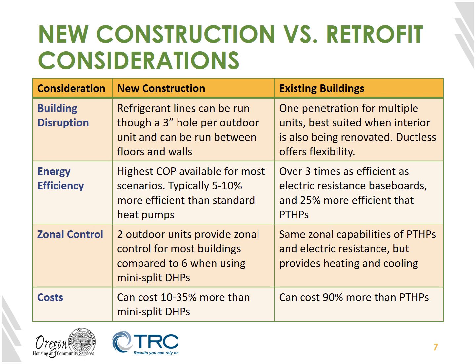Now, there are some realities to consider here. VRF systems are more expensive. They typically do cost somewhere in the range of 24, 25% more than a ductless heat pump multi-split system for a building in new construction. And in existing, if we're comparing to package terminal heat pumps, they can be as much as 90% more expensive. Because of the way the systems are designed, where they do not have a home run refrigerant line going directly from the indoor unit to the outdoor unit, and instead they have a branching configuration of refrigerant lines, there are also some additional safety requirements that come into play. And the larger the building, the more likely these safety requirements come into play, because there are limitations to how much potential refrigerant leakage you could have based on how many different connections you have.